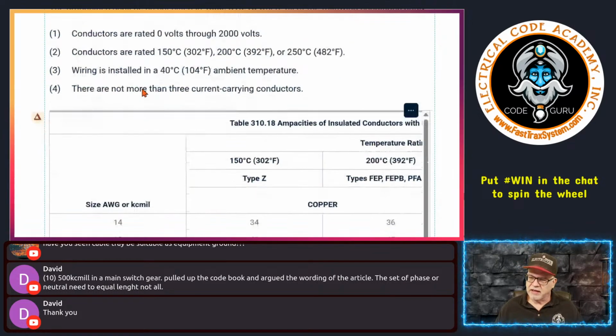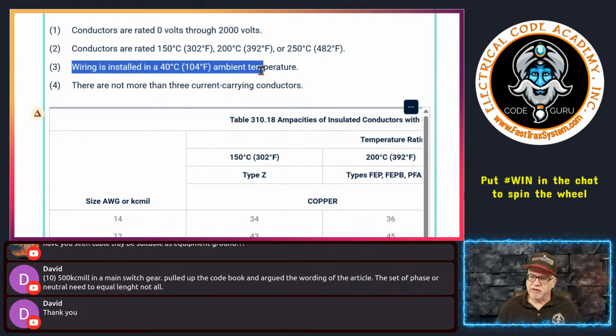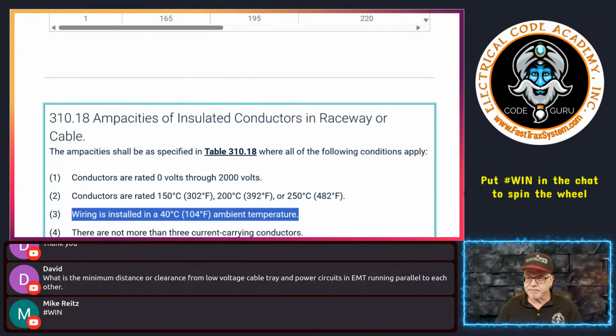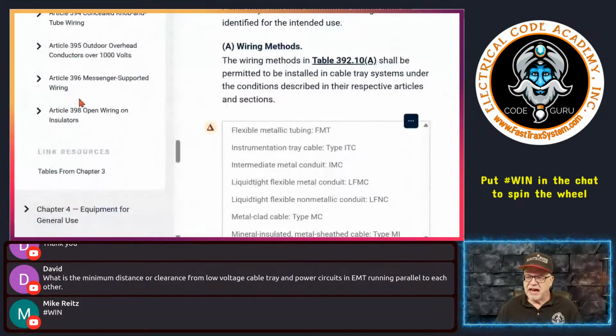This is dealing with the ampacity of insulated conductors rated for a cable. This is the ampacity here, as long as you meet these conditions, okay? And these have temperature values that are in 40 degrees C. These are not typically what we're going to use as a normal installation. Our normal installation is going to be THHN, XHHW type conductors inside of cables, the normal cable allowance. However, it is important, and I don't know if this will go back. No, it's going to make me jump all the way down again. Okay, I just think it's important to understand its premise here.